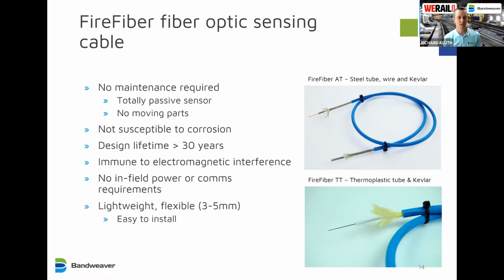Moving on to the sensing cable. As we said, the sensing cable is based on standard telecoms fiber. It means it's totally passive, no moving parts, so no maintenance is required. It's not susceptible to corrosion. So this cable's lifetime is often in excess of 30 years. Other benefits of the fiber optic cable is it's immune to electromagnetic interference, no in-field power or communications requirements, which reduces any additional cost and increases the reliability. It's very lightweight and flexible. Typically, these are in the region of a 3 to 5 millimeter diameter.